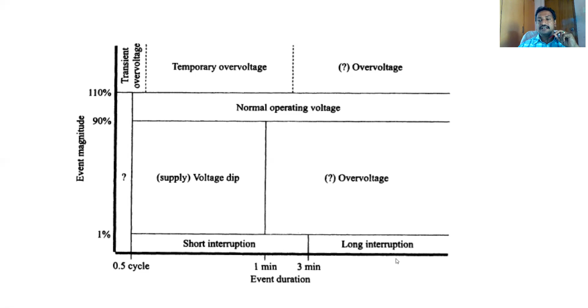Next, we'll come back. Similarly, here, if it is below 0.5 cycles, above 110%, transients; 110 to 90%, there is no issue. If below 90% of the voltage is there, such a decrease in the voltage is called a notch, also called a transient. Already I told you, notch or transients are very short duration variations in the power frequency or power voltage. Then in this scenario, below 3 cycles, momentary; below 1 minute, temporary; above 1 minute, sustained interruption. If it is above 110%, momentary swell, up to 3 seconds, and up to 1 minute, temporary swell. Similarly, if it is below 90%, momentary voltage sag; more than 3 seconds, less than 1 minute, temporary voltage sag.